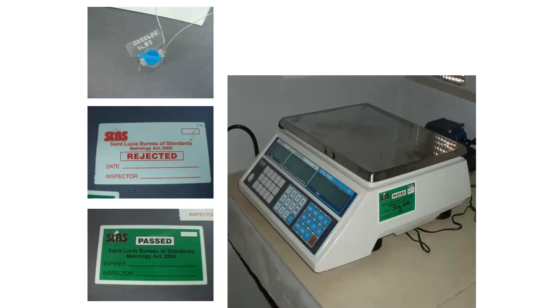When we do our verification, we pass or reject the scale depending. Some weighing devices also have the capability to allow for sealing. So we place a seal on the device to prevent tampering that would probably change the parameters of the scale after we have left. Some devices may also have an audit trail, so we can see if any changes were done to the instrument in a subsequent verification.